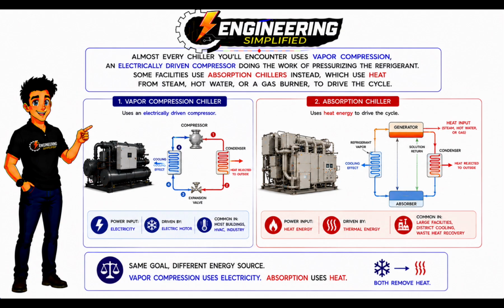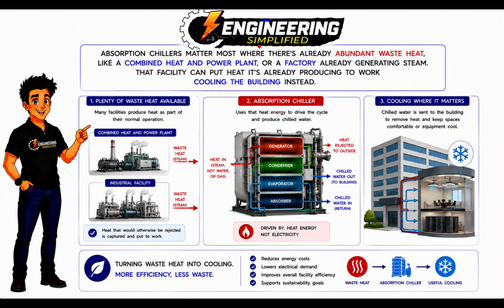Almost every chiller you'll encounter uses vapor compression, an electrically driven compressor doing the work of pressurizing the refrigerant. Some facilities use absorption chillers instead, which use heat from steam, hot water, or a gas burner to drive the cycle. Absorption chillers matter most where there's already abundant waste heat, like a combined heat and power plant, or a factory already generating steam. That facility can put heat it's already producing to work cooling the building instead.